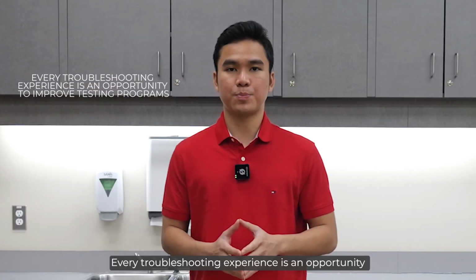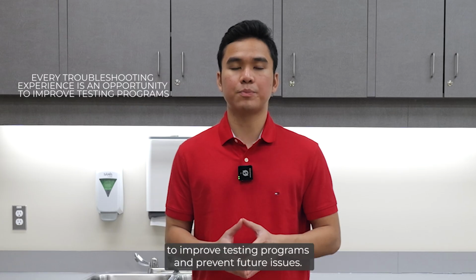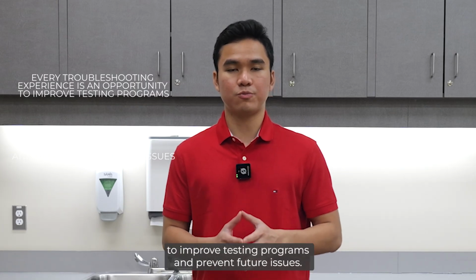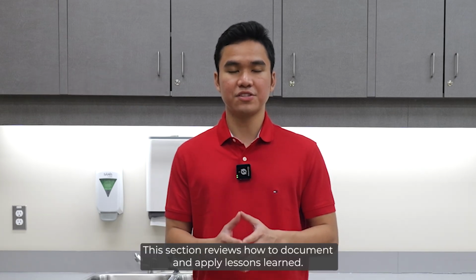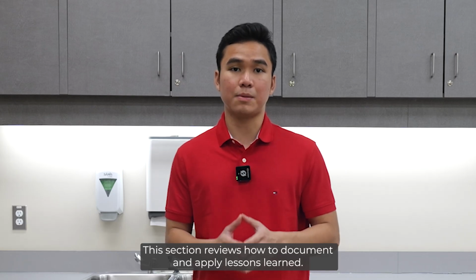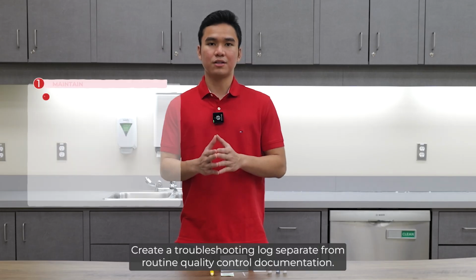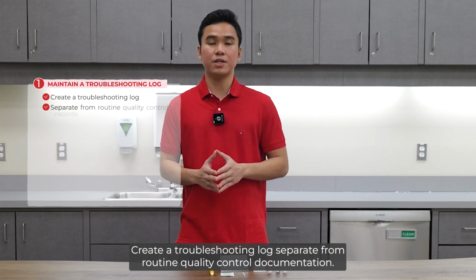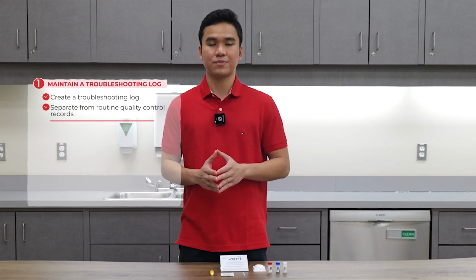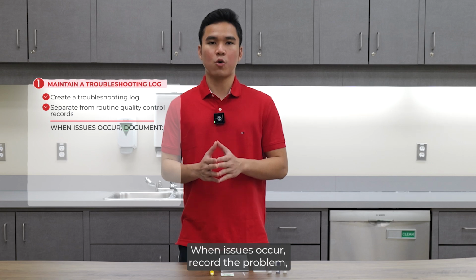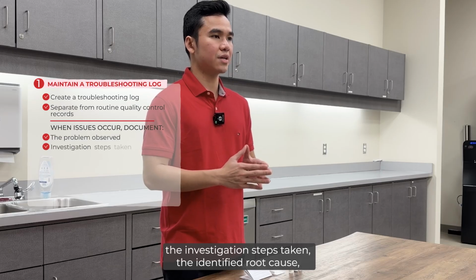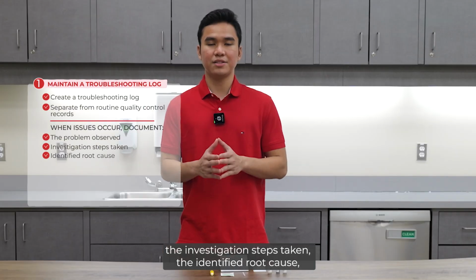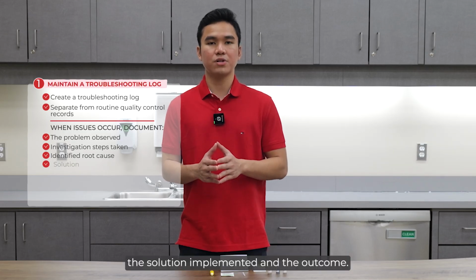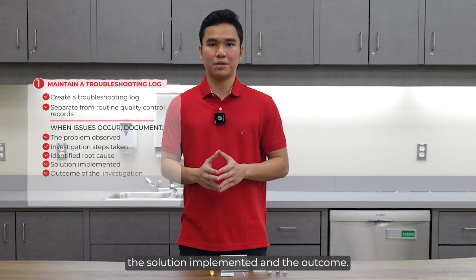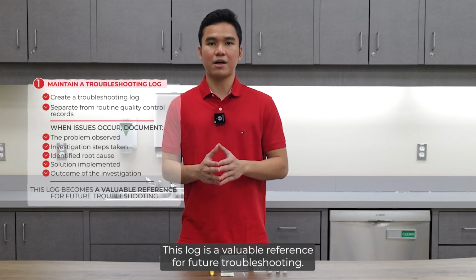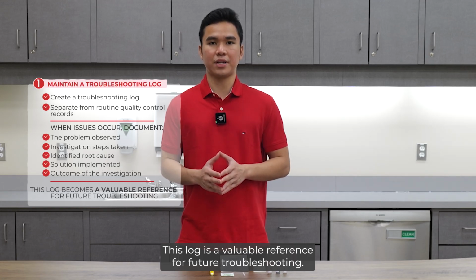Every troubleshooting experience is an opportunity to improve testing programs and prevent future issues. This section reviews how to document and apply lessons learned. Create a troubleshooting log separate from routine quality control documentation. When issues occur, record the problem, the investigation steps taken, the identified root cause, the solution implemented, and the outcome. This log is a valuable reference for future troubleshooting.